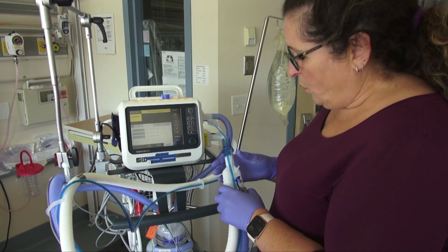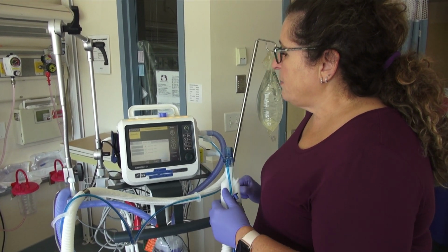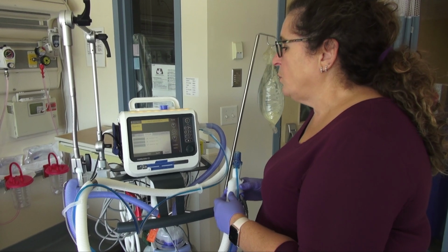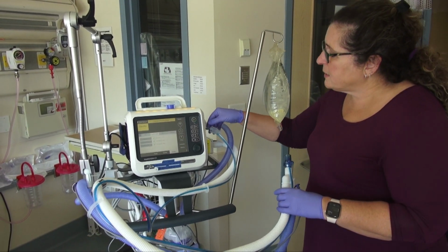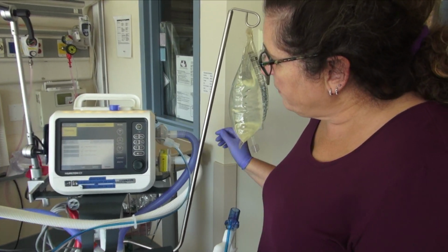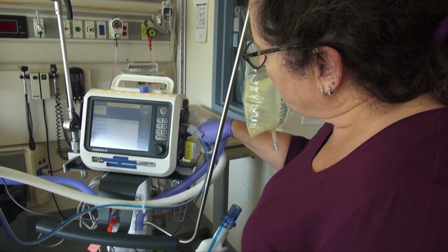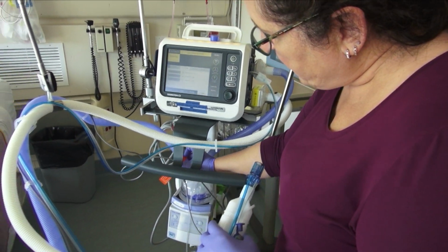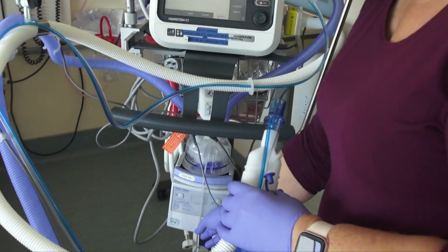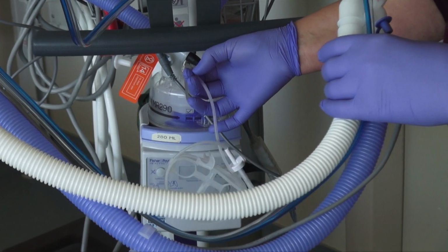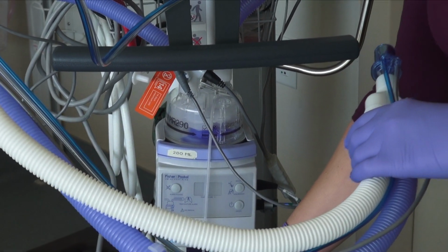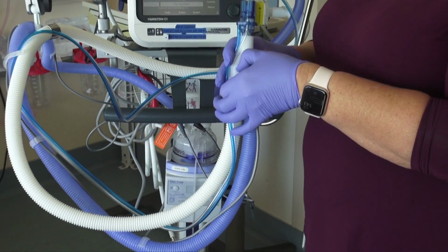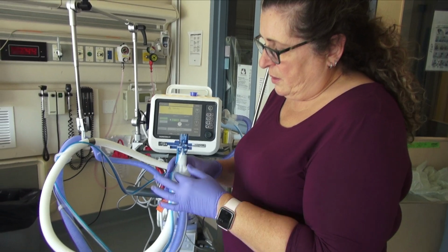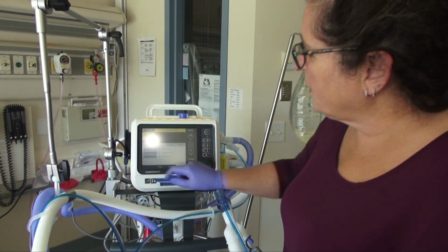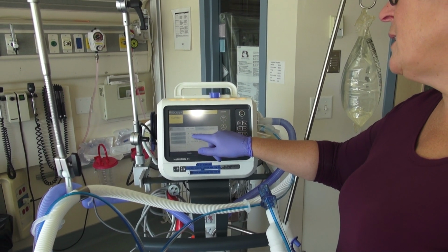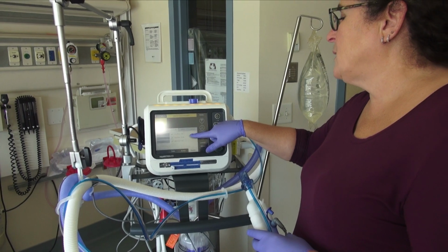If you get a green check mark, you are good to go. If you get a red X, that means somewhere in this system there is a leak and you need to run through. Some of the places where there can be leaks is if the flow sensor is not tight enough, if the expiratory valve is not put in tight enough, if your temperature probe is not placed in properly, and if your spike is allowing air out, it shouldn't, because it should still be in the spike package, or if one of these things is left open. Those are things to check for. In this case, we passed, so the leak test, there are no leaks. We have a date and a time that it has passed.